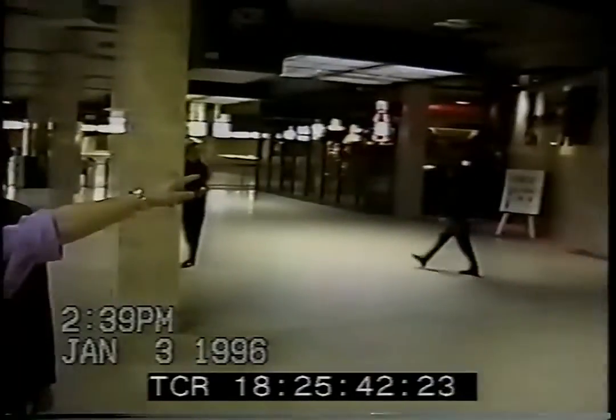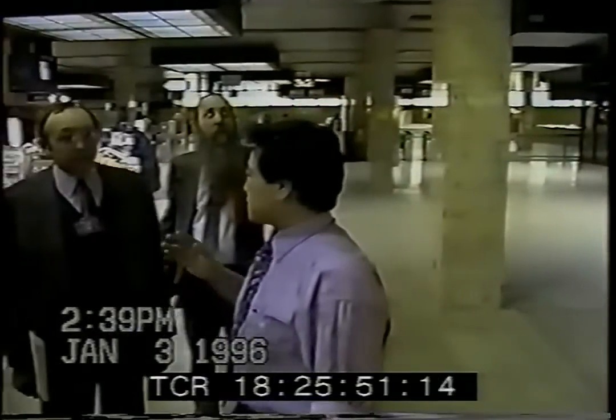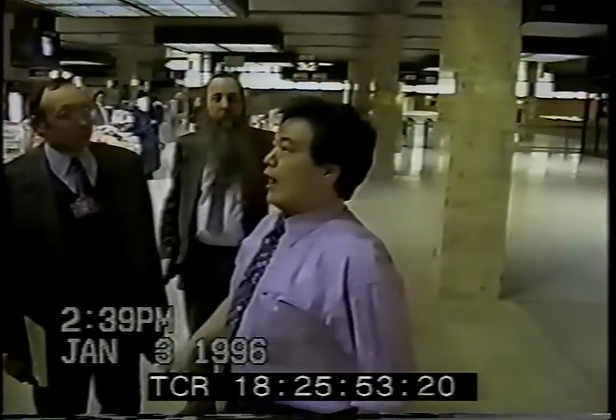Okay, this is the PATH dome. And what we are intending to do here is a couple of things. First, we're going to put a 3-foot baffle underneath the ceiling area there as a smoke trap. 3-foot, something like 24 inches or whatever. And we want to maintain like a 7.6 height clearance. And right underneath this dome, this is going to be redone.